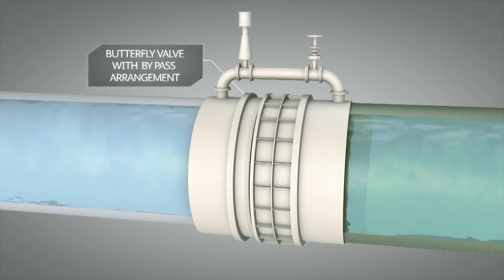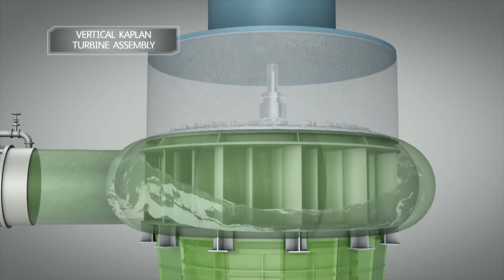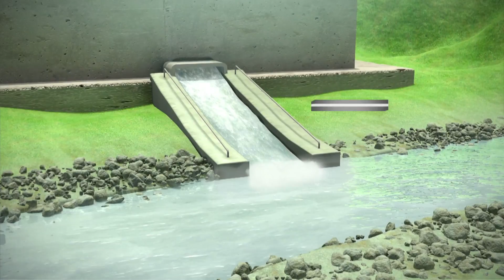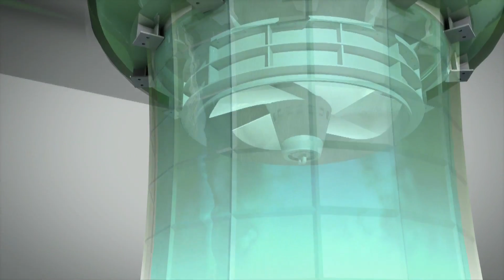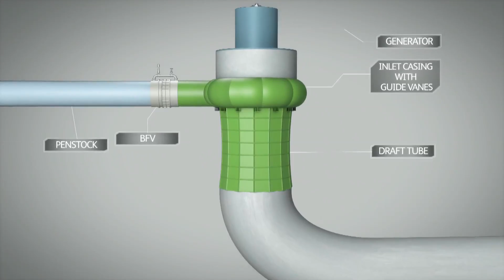At the inlet and outlet of the penstock, valves are provided to control the flow of water. The water enters the turbine, dissipates the energy it had developed during its fall, and is discharged back into the river or canal through a channel from the powerhouse called the tail race. The water from the turbine is guided onto the tail race through a structure called the draft tube.